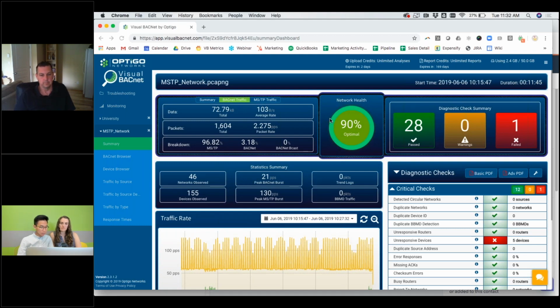And what causes that to be an unconfirmed COV? Is that it's shooting out its information because the value changed by whatever the COV was set at, and then nothing replies back to it? Is that what's giving it the unconfirmed COV? That's correct. Yeah. Unconfirmed is so that no one would need to respond, and it's not expecting a reply. Right. Okay, so it's not expecting one, so it's fine.